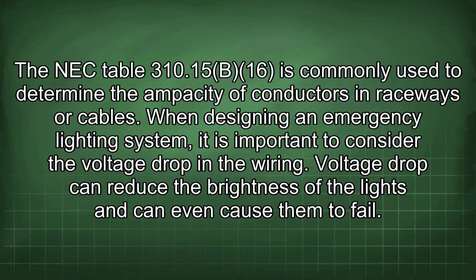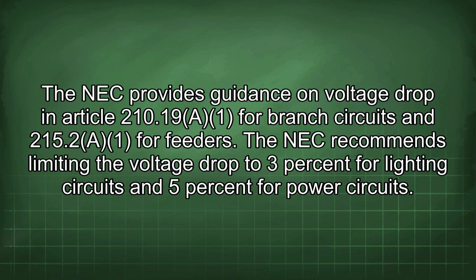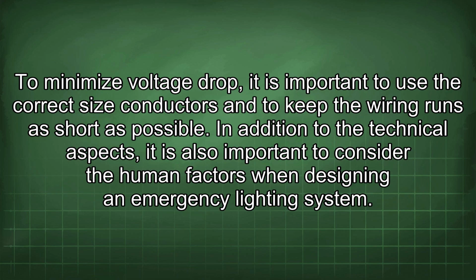When designing an emergency lighting system, it is important to consider the voltage drop in the wiring. Voltage drop can reduce the brightness of the lights and can even cause them to fail. The NEC provides guidance on voltage drop in Article 210.19(A)(1) for branch circuits and 215.2(A)(1) for feeders. The NEC recommends limiting the voltage drop to 3% for lighting circuits and 5% for power circuits. To minimize voltage drop, it is important to use the correct size conductors and to keep the wiring runs as short as possible.